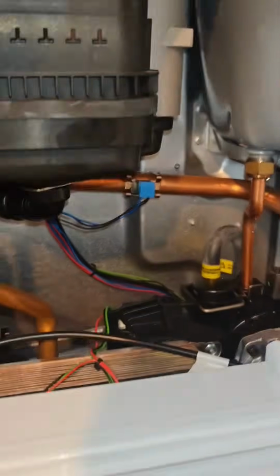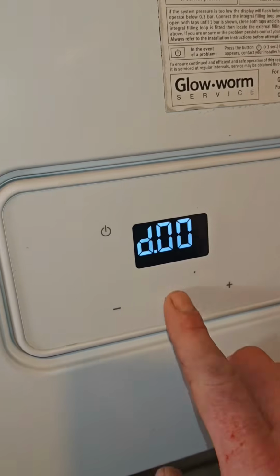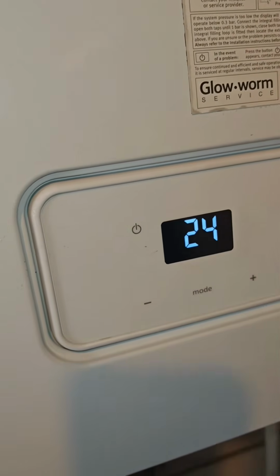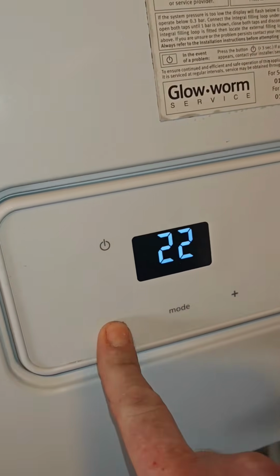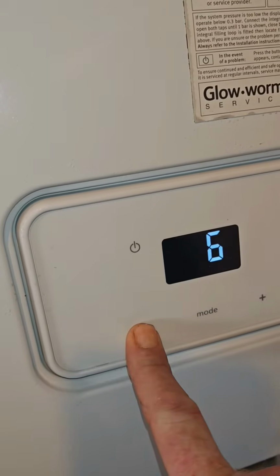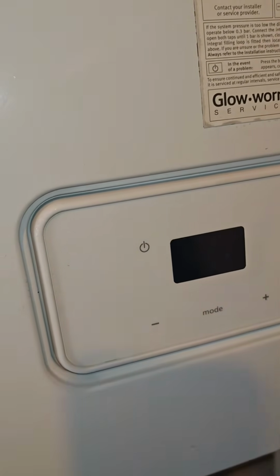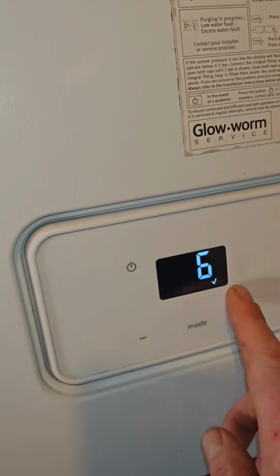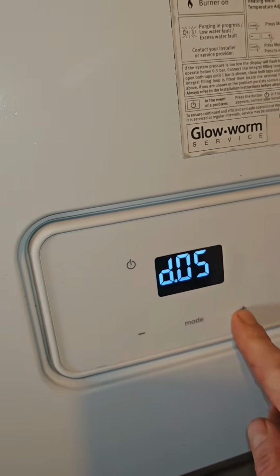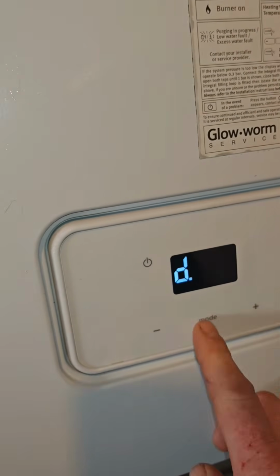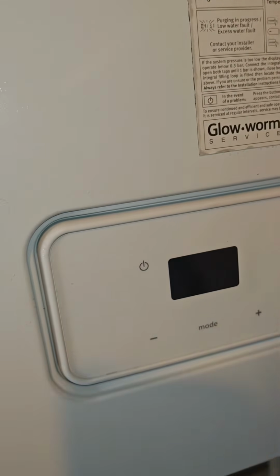The radiators have been bled around the house and we are running the air purge cycle. Right, I can now enter the diagnostics menu to check that the boiler's running efficiently and it's all set up correctly. That no, this one's not. So I've worked out how much heat the house actually needs, and I'm gonna adjust the boiler. So the boiler's burning the correct amount of gas and the pump is running at the correct speed. So all this is gonna save us energy.